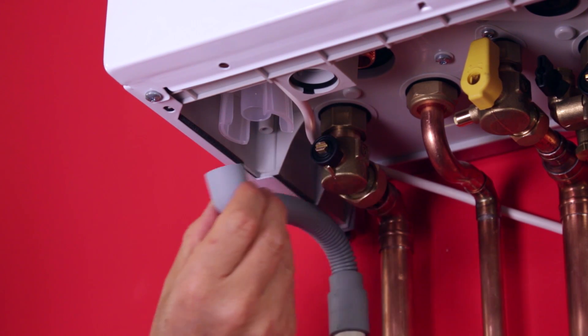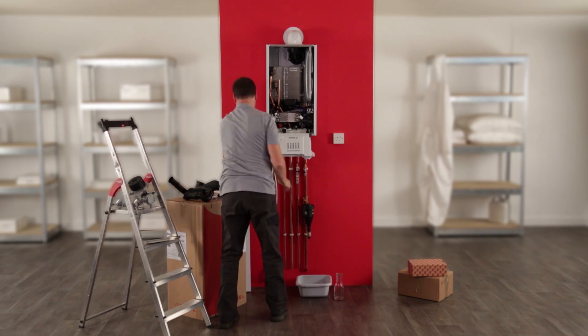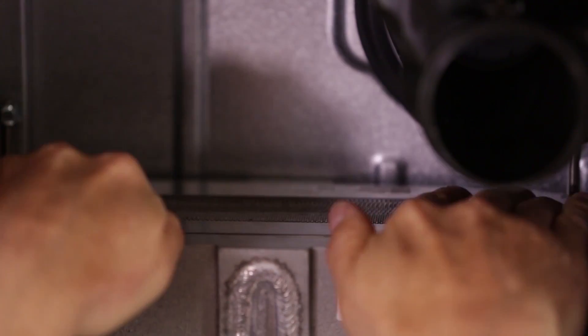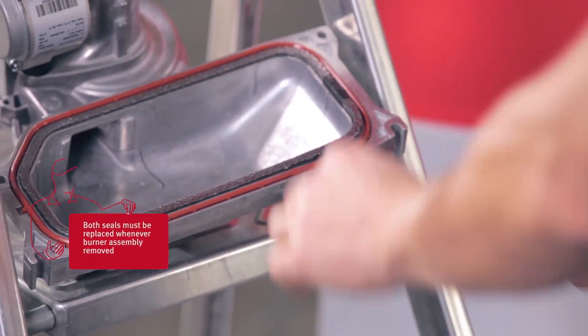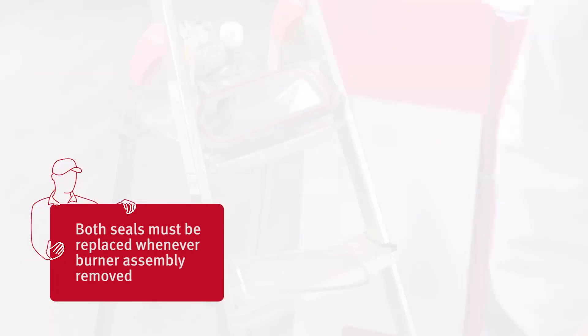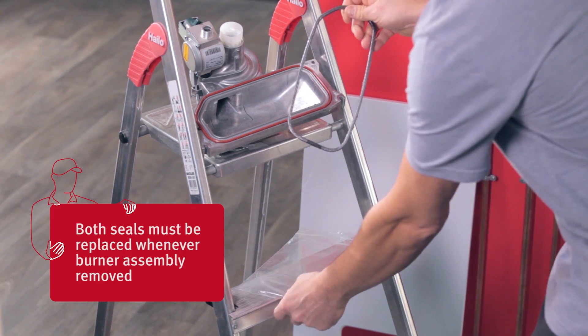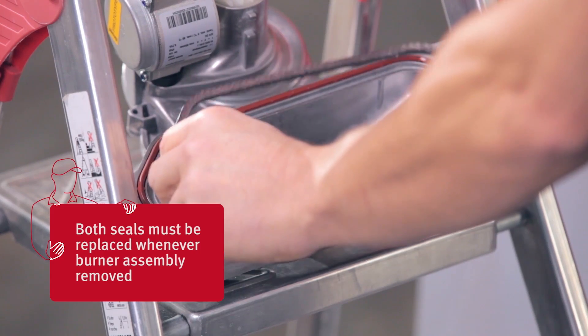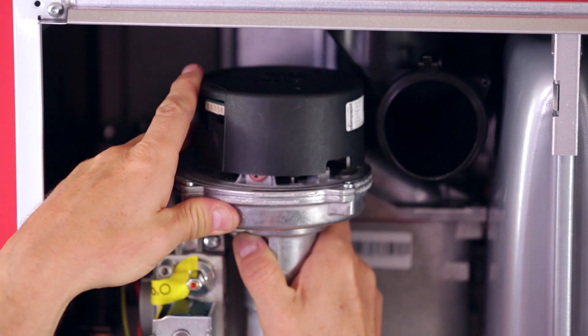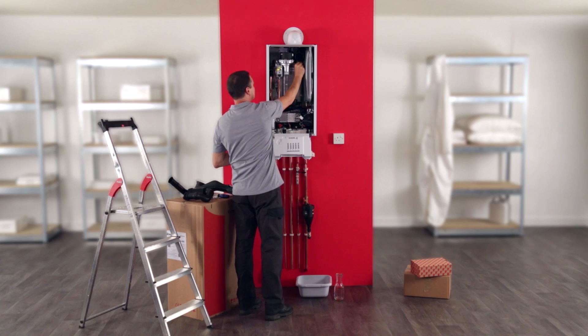Finally, you can reassemble the condensate trap. Then simply position the burner grid on the top of the heat exchanger. Remove the old graphite seal and the silicone seal from the burner door and replace them with new seals. Reposition the burner door on the top of the heat exchanger and tighten the four fixings.